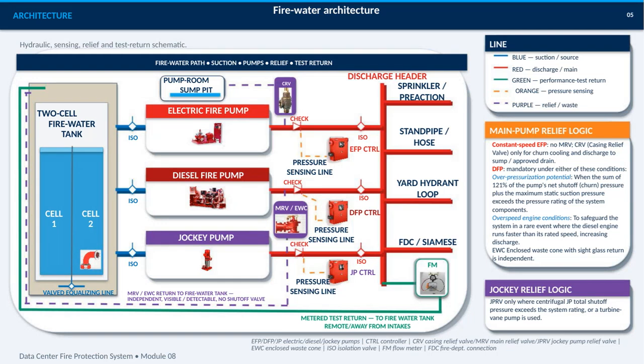The design begins with a two-cell firewater tank, with a valved equalizing line between cell 1 and cell 2, providing a shared source for the system. Blue lines represent suction, feeding the electric fire pump, diesel fire pump, and jockey pump. Each pump includes isolation and check functions, with controls shown separately, and all discharge flows into the common discharge header.